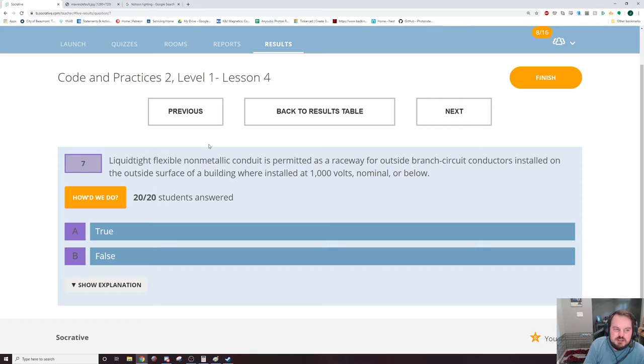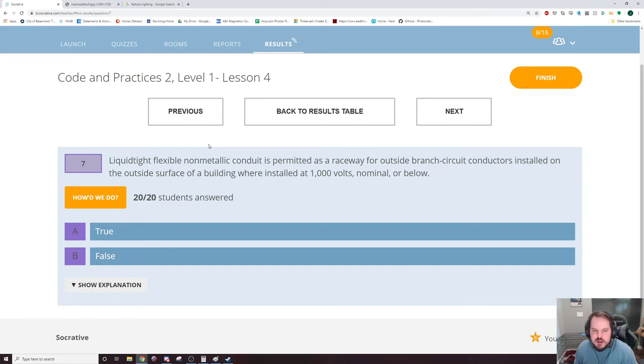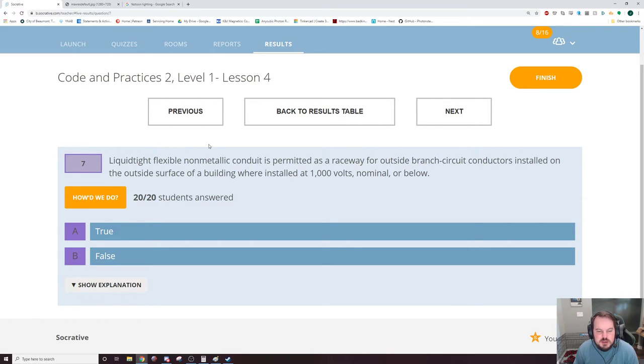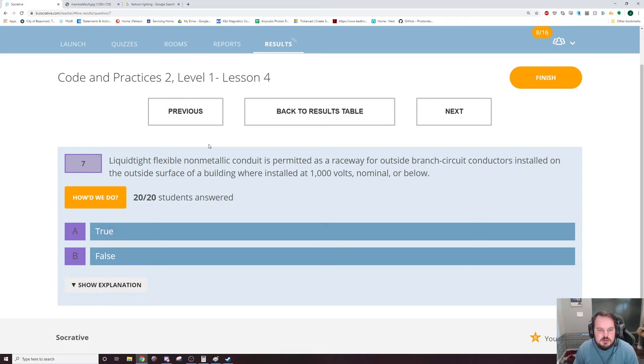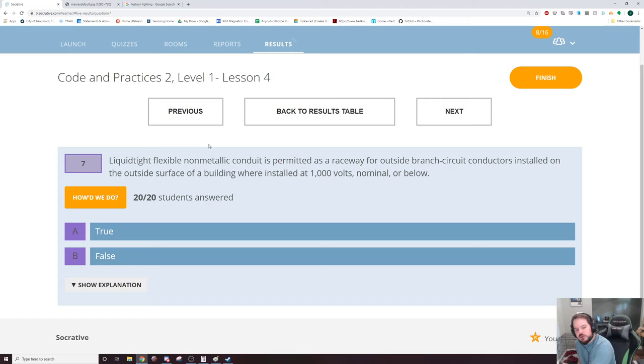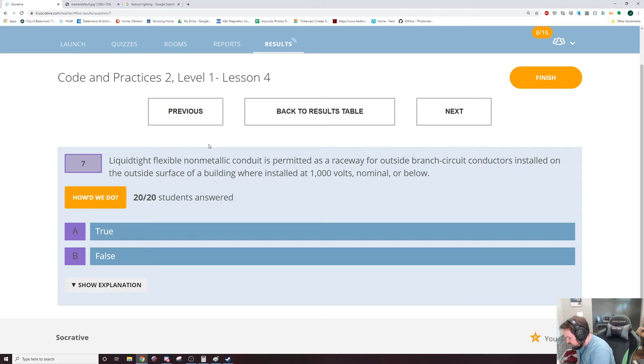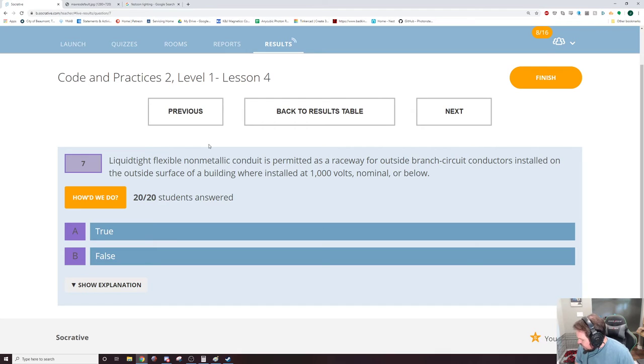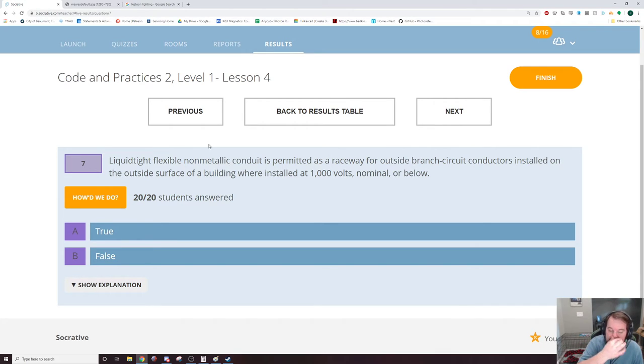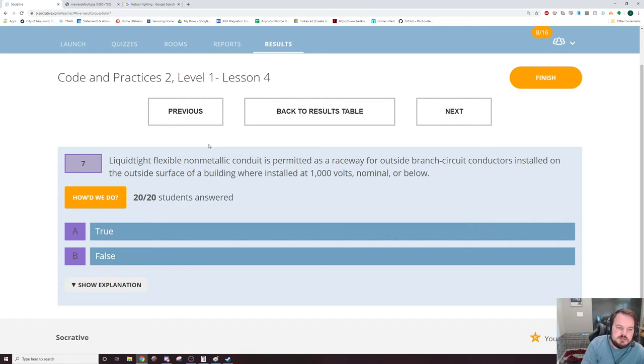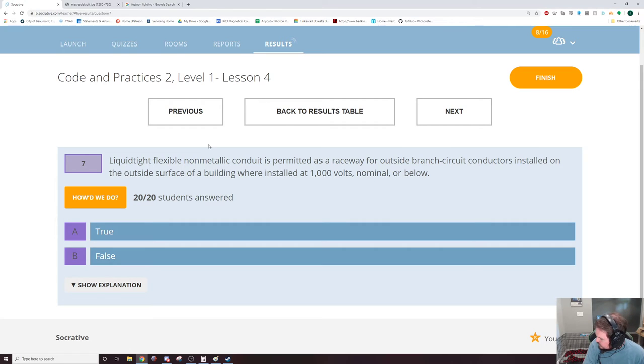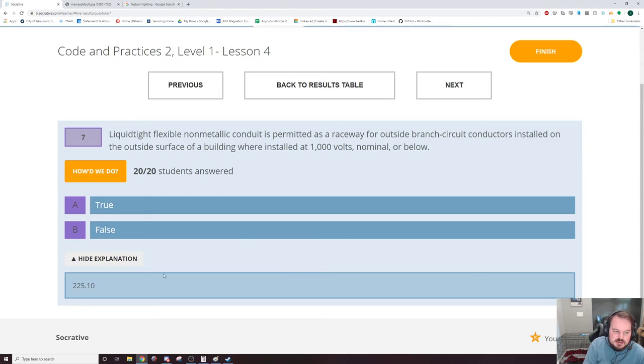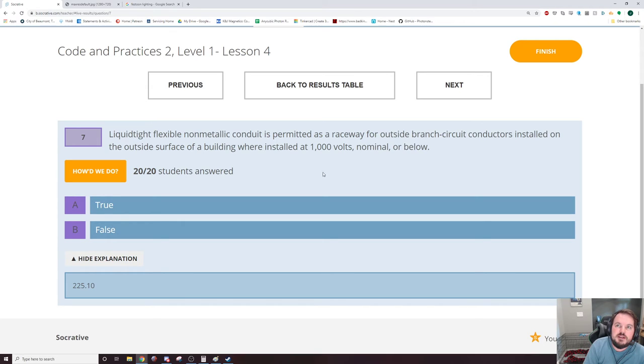Next up is seven liquidtight flexible nonmetallic conduit is permitted as a raceway for outside branch circuit conductors installed on the outside surface of a building, where installed at 1000 volts nominal or below. This one is in the outside branch circuit, so 225. And it's like right there at the very beginning of the section. 225 covers wiring on buildings or other structures, and it has just a list of things you can use with outside branch circuits and feeders. It's just a straight up list. 225.10 is where that is, if you would like to look that up.